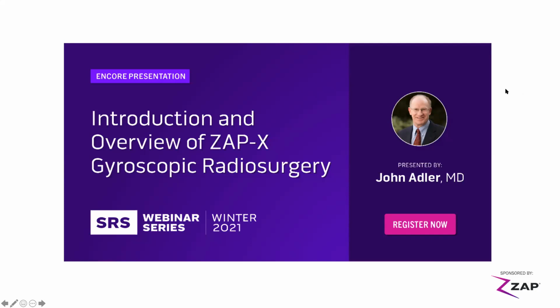Okay. In case of a power outage during a treatment, how does ZAP-X handle the situation? The door comes down automatically, and we can extract the patient in less than about 30 seconds. I mean, that was the time frame that the FDA required us to do it. So it's every bit as fast as your ability to get in and out of a radiotherapy vault that has this big lead door on it.